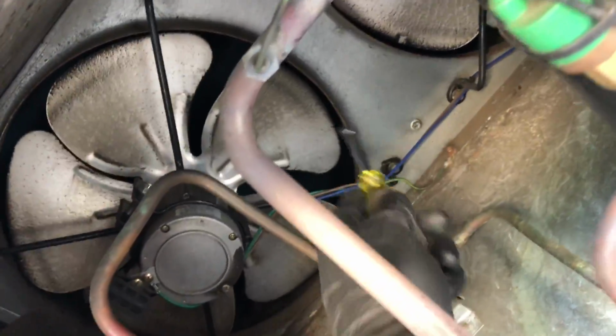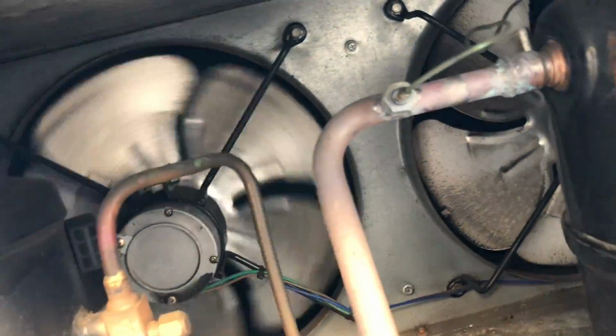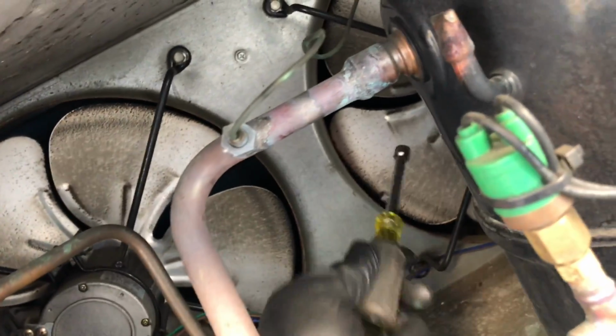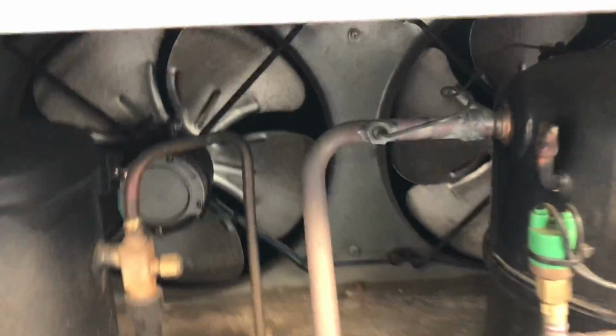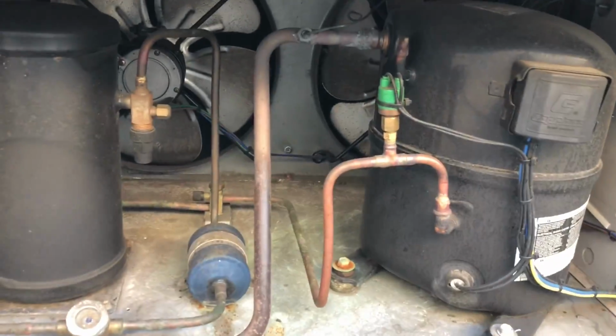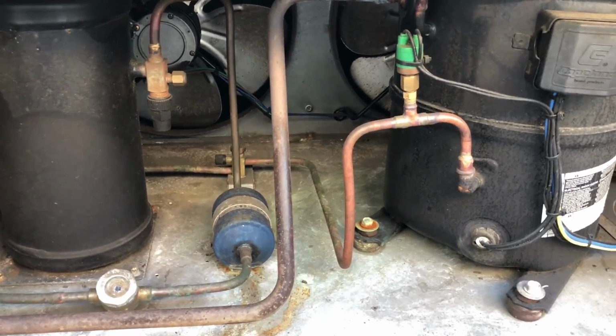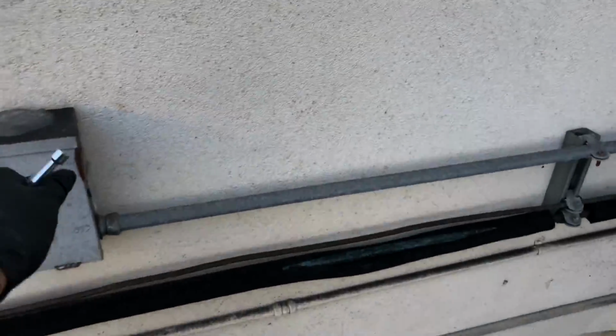Oh yeah, definitely a failed condenser fan motor somewhere. Trying to get that one jump started. Nope, they're both gone. So it just cycled back on from high head pressure. I got 2 dead condenser fan motors. Turn the disco off and see. I got to hustle up some motors here.